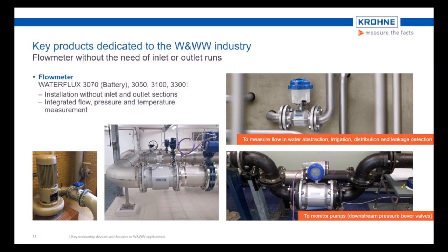Without exception, you can install the flow meter directly after a pump, which the application picture on the left-hand side is showing, or even a double 90-degree bend is possible, showing the customer application picture on the right-hand side. Another important feature of this water meter is the option to have an integrated pressure and temperature sensor, which can be used to monitor leakages during the night. A pressure drop in one DMA, district metering area, could indicate a possible leakage, therefore an action is required. A pressure drop in multiple DMAs at the same time can have another root cause, for example a national TV event like a football match, where no action is required then.